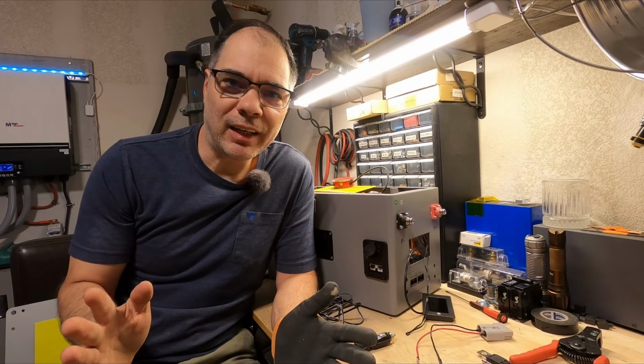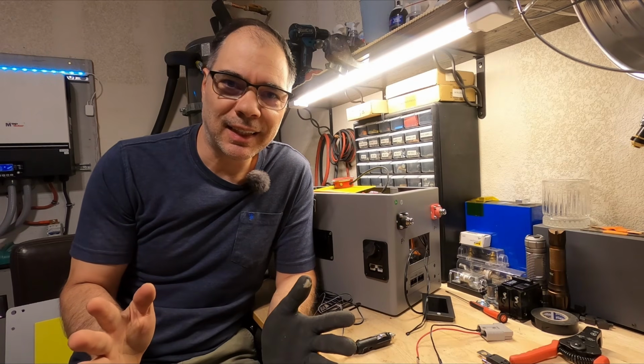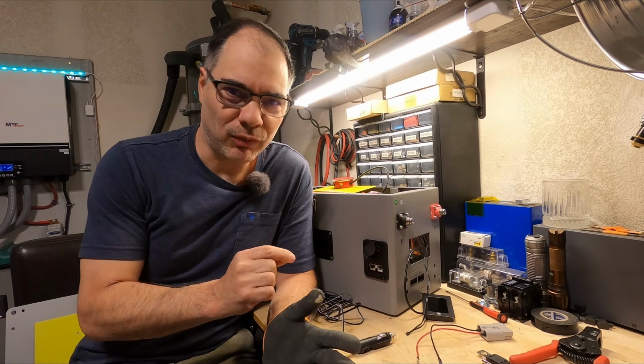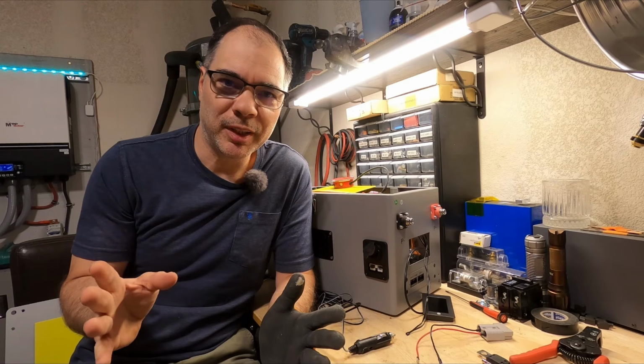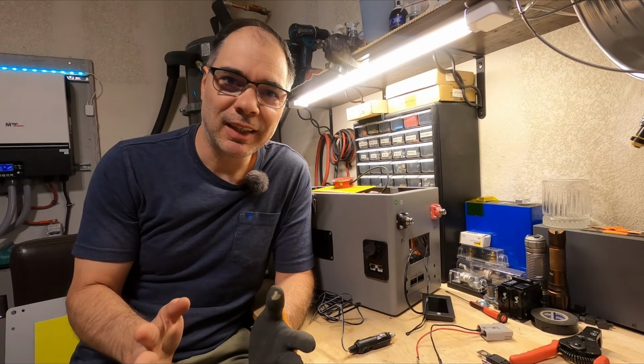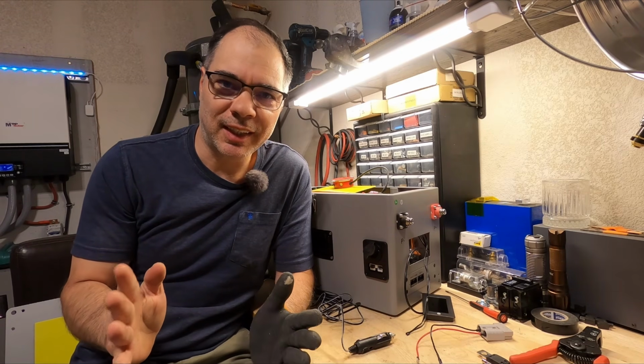Now, since the delay on the overcurrent protection is set to 10 seconds, I think that's far too long for that small of wire - it might melt before the BMS actually kicks in. So I'm expecting the short circuit protection to kick in on this one.